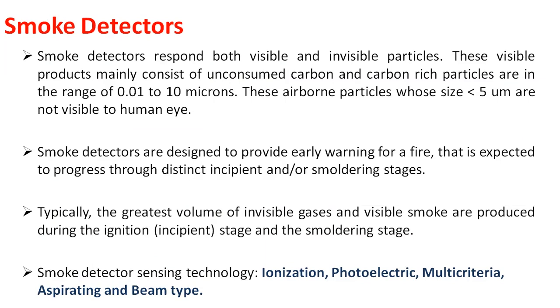Smoke detectors respond to both visible and invisible particles. Visible products mainly consist of unconsumed carbon and carbon-rich particles in the range of 0.01 to 10 micrometers. Invisible particles whose size is less than 5 micrometers are not visible to the human eye. Smoke detectors are designed to provide early warning for fires expected to progress through distinct incipient and smoldering stages. The incipient stage is where invisible gases are evolved, and the smoldering stage is where visible smoke is produced.